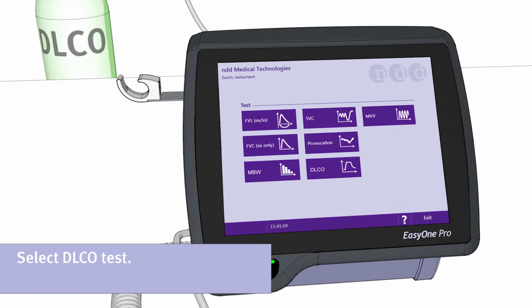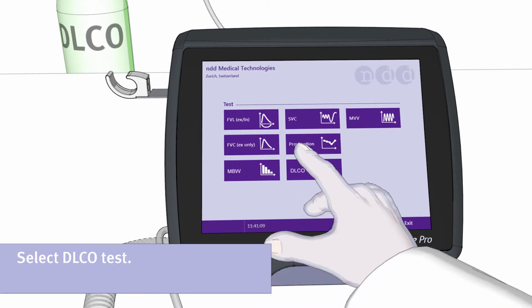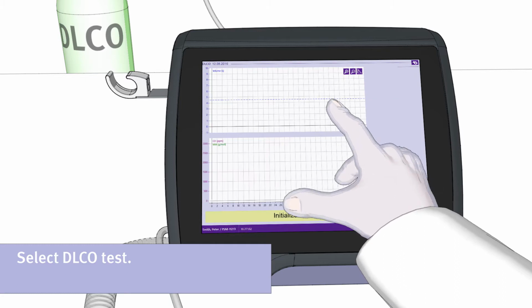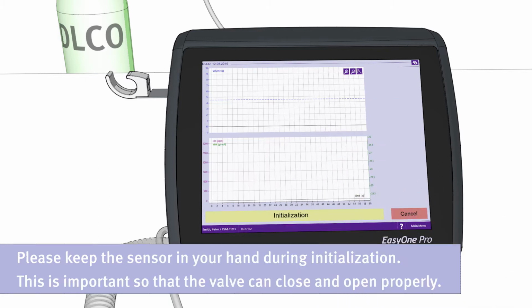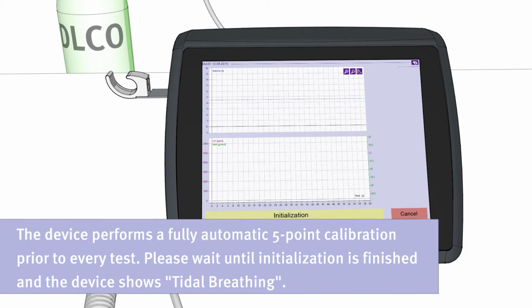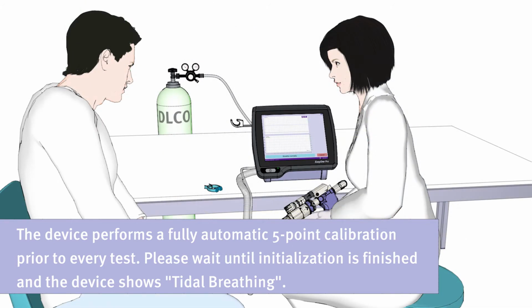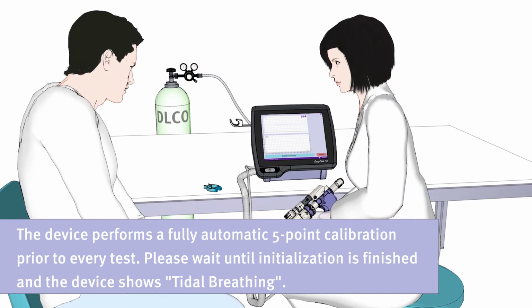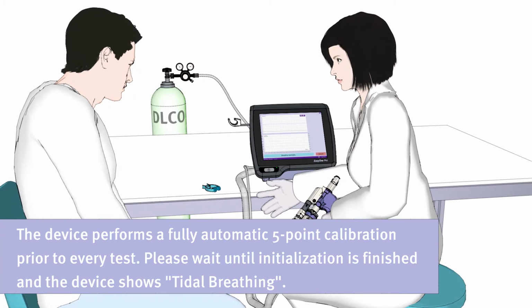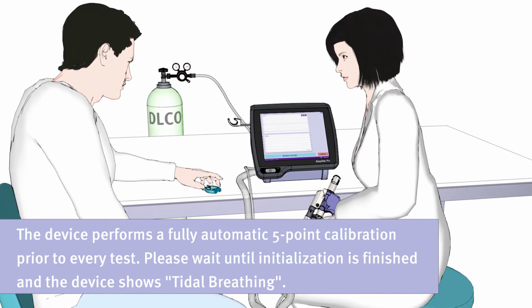Please press the button DLCO to start the respective test. Keep the sensor in your hand during initialization. This is important so that the valve can close and open properly. The device performs a fully automatic 5-point calibration prior to every test. Please wait until initialization is finished and the device shows tidal breathing.